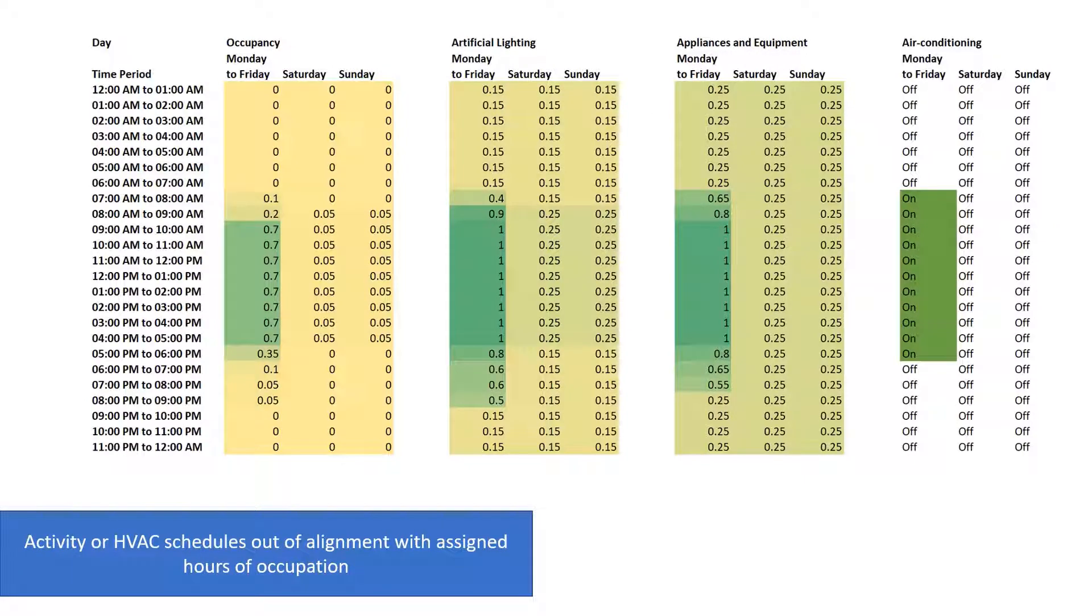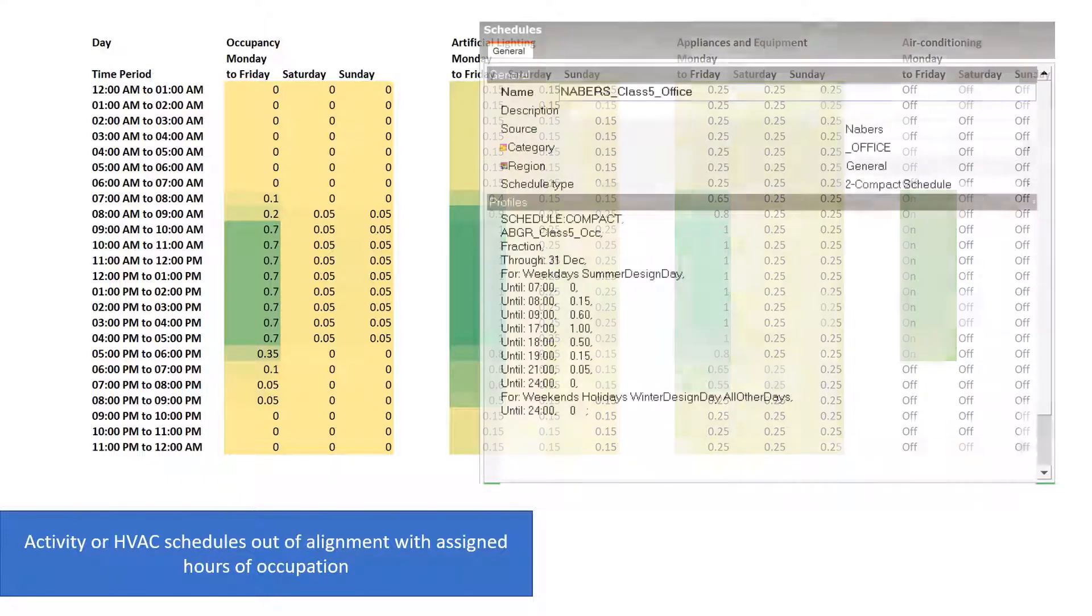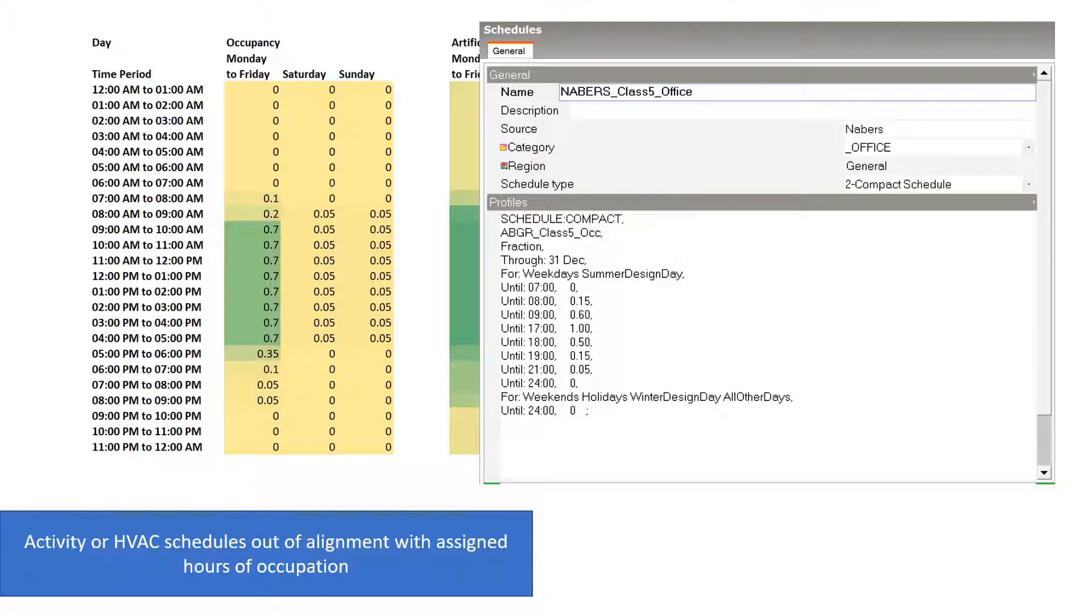If the report shows an unexpectedly large number of occupied hours outside the target temperature range, it is worth double checking that the activity and air conditioning schedules for your building model match the assigned NCC building class of the space. If these schedules are out of alignment, the plugin could be analysing hours where the mechanical systems are not working.